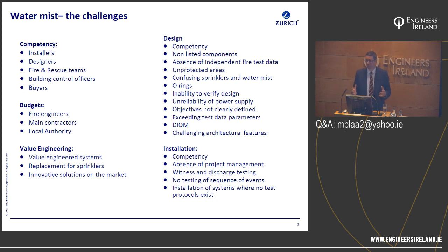And we come across buildings, large buildings, high-rise buildings, where there are complex cause and effects matrices associated with the sequence of events. And I ask the question, where is the interaction between the water mist system, bringing down the lifts, closing the doors, shutting off the gas valves? It's my experience that none of that interaction between the mechanical side of the project, the water mist side, and the electrical side, and the sequence of events ever gets proven and tested. And I think it's a wider issue within the construction industry that we've got systems out there where we've not got coordination between contractors and lines of responsibility.